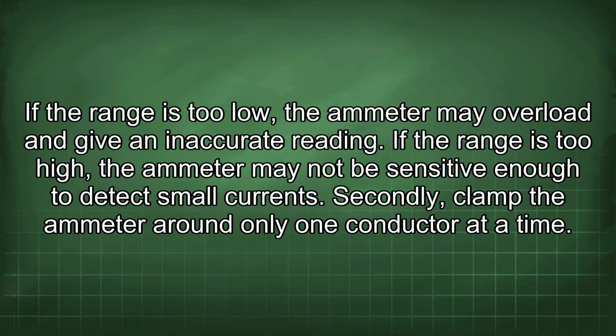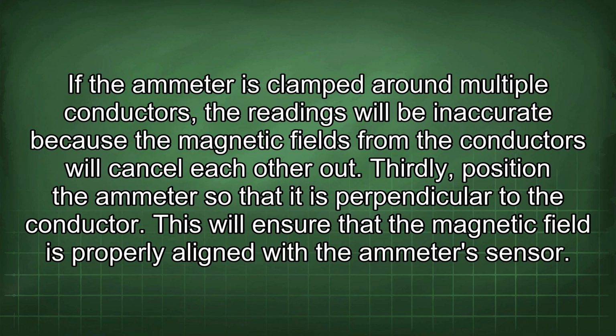If the range is too low, the ammeter may overload and give an inaccurate reading. If the range is too high, the ammeter may not be sensitive enough to detect small currents. Secondly, clamp the ammeter around only one conductor at a time. If the ammeter is clamped around multiple conductors, the readings will be inaccurate because the magnetic fields from the conductors will cancel each other out.